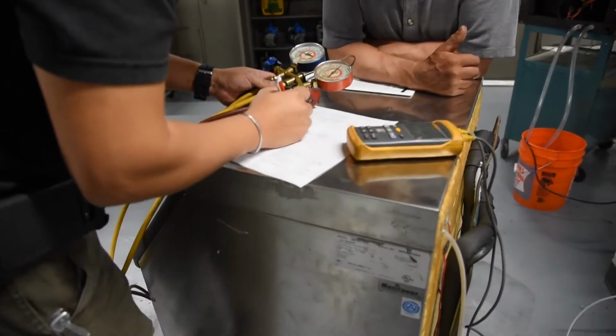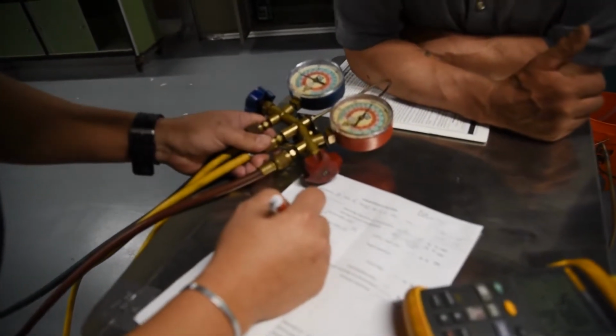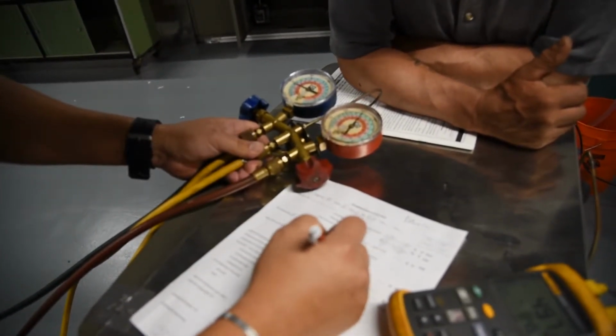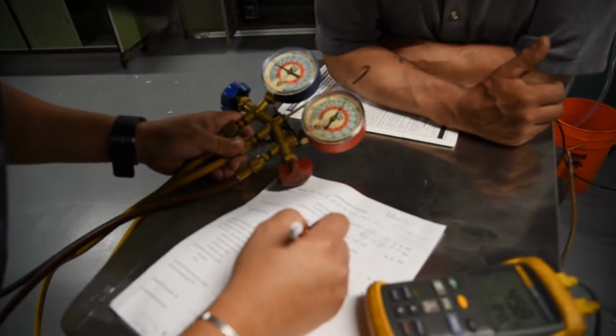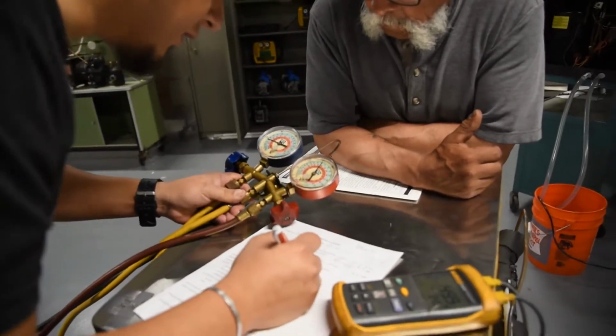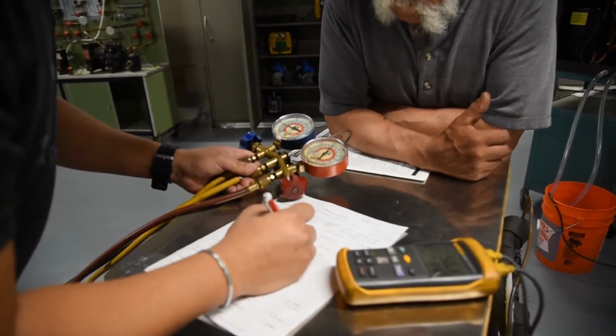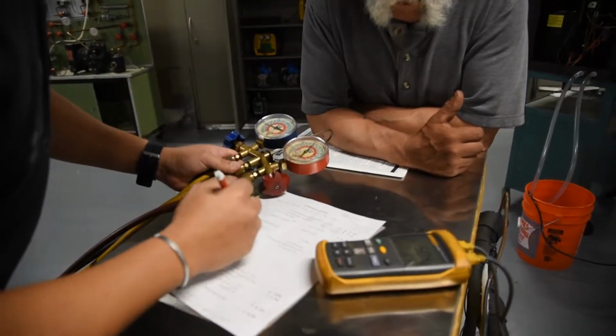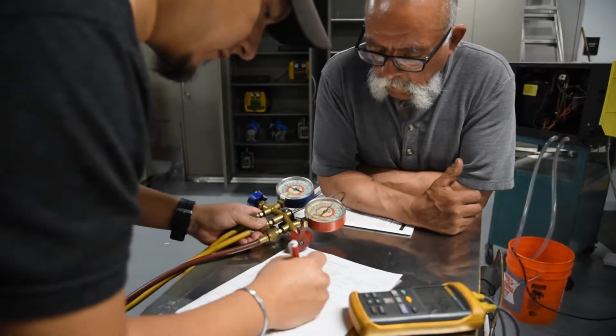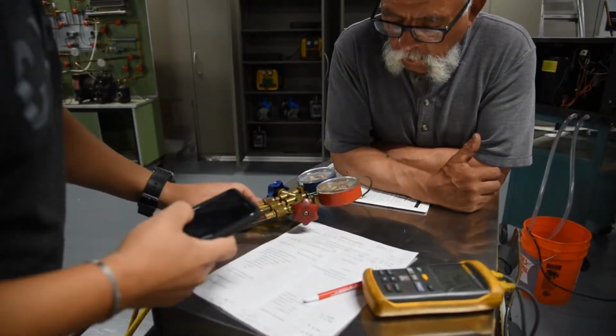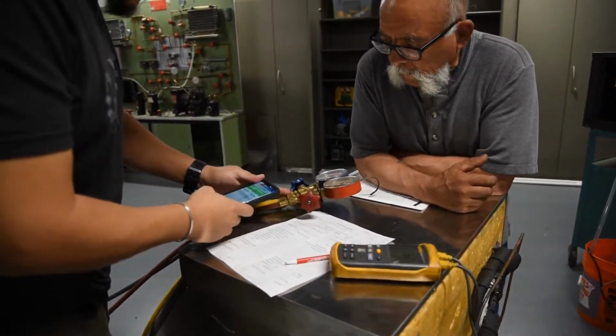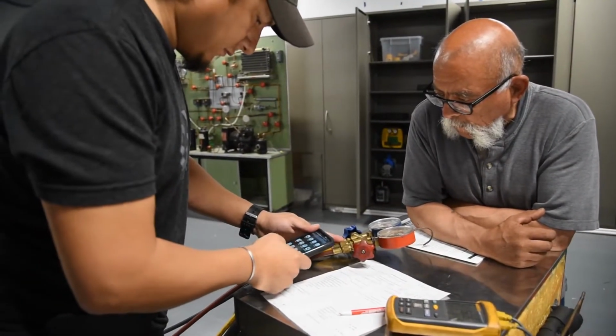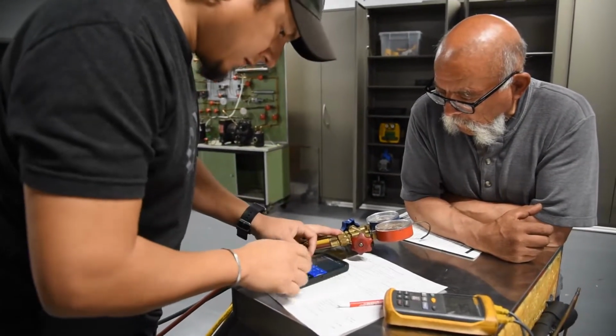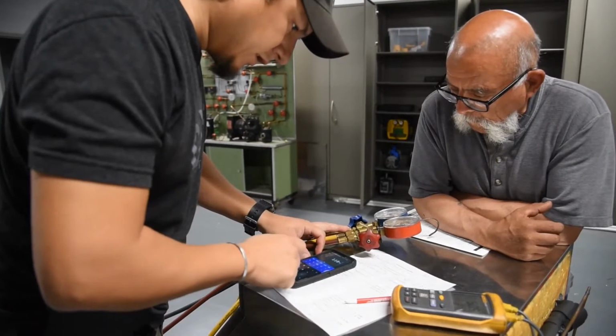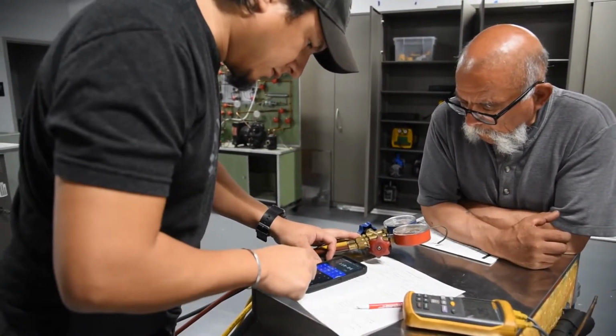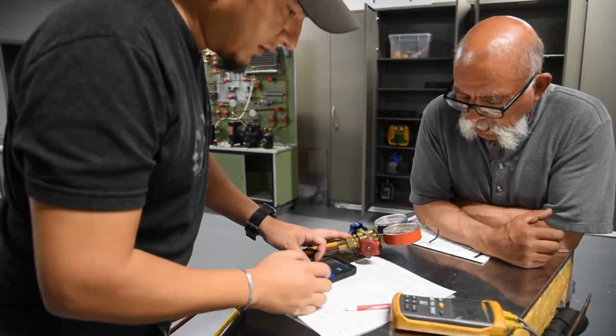Okay. So high side PSIG, we have 310. Saturation temperature is 118. Condenser line temperature is 84. So we have a big differential here also. So 118 minus 84, we have 34 of subcooling. Okay?